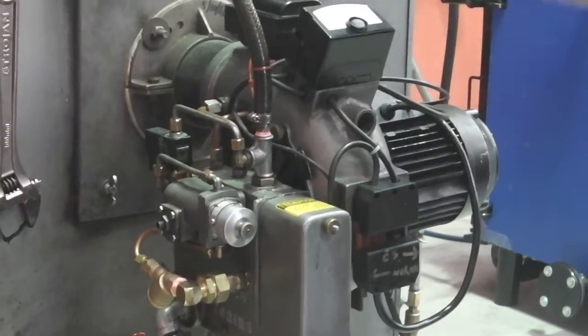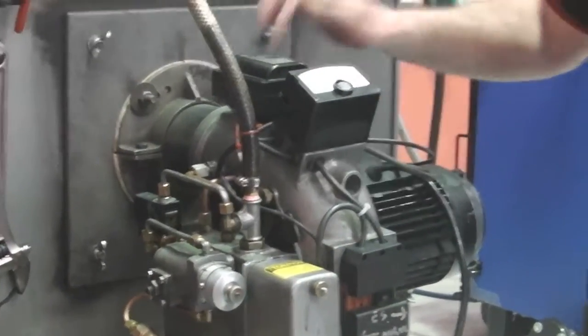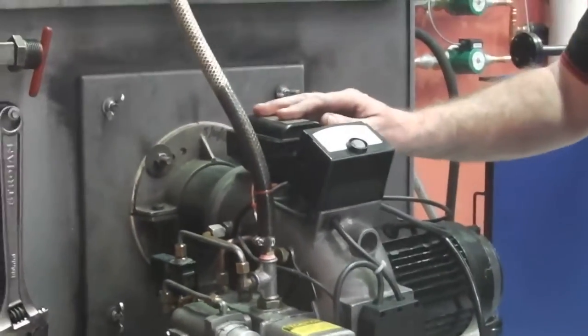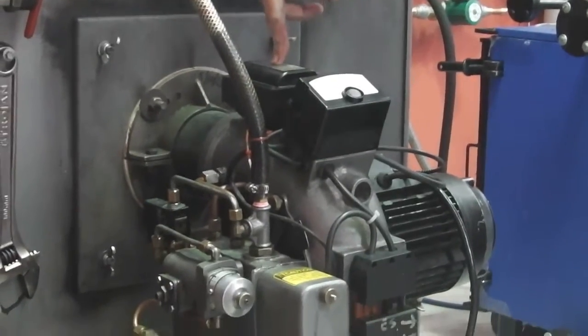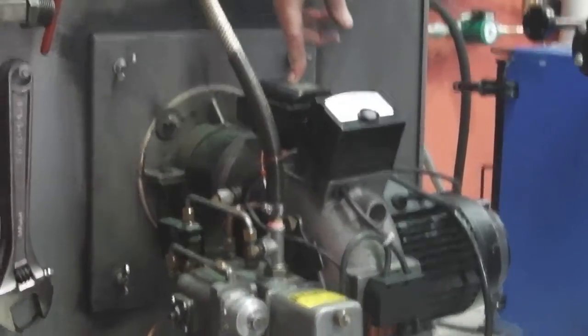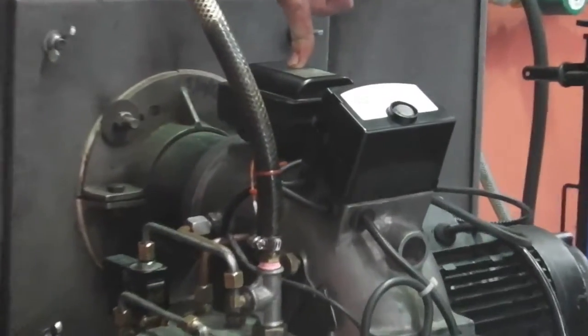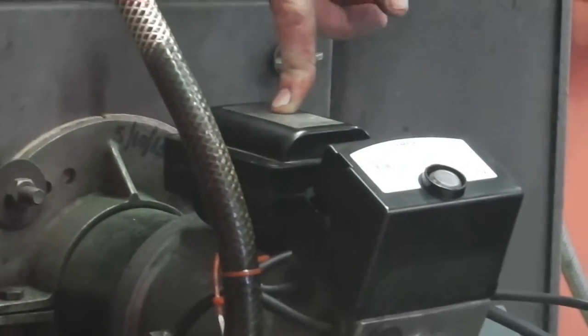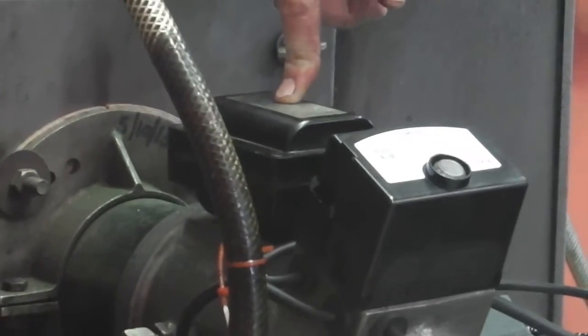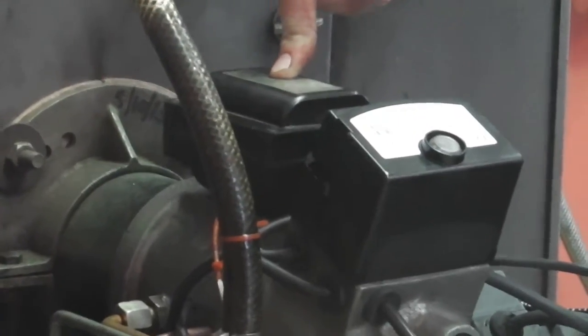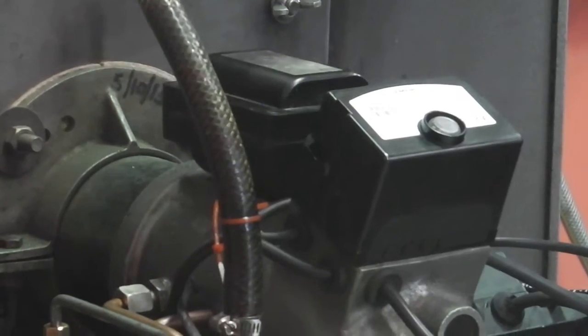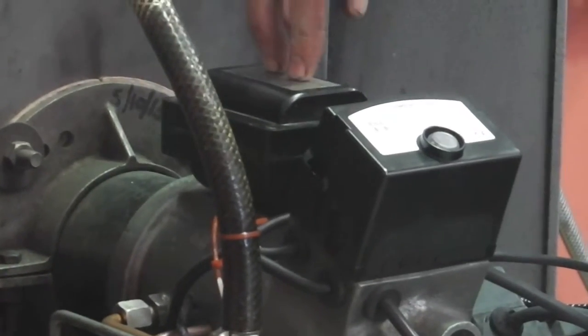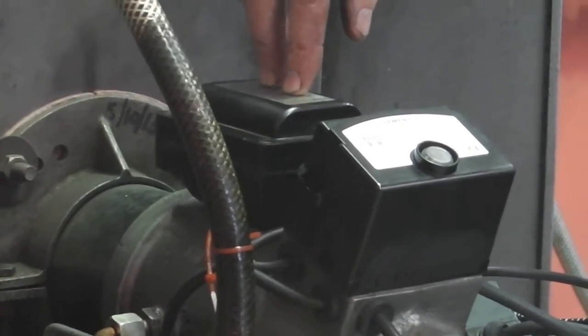The next thing is, up here on the top of the burner gun, there's two big black boxes. This guy here is the ignition transformer, and that ignition transformer produces a spark inside, near the nozzle, across the electrodes of the burner at start-up time.